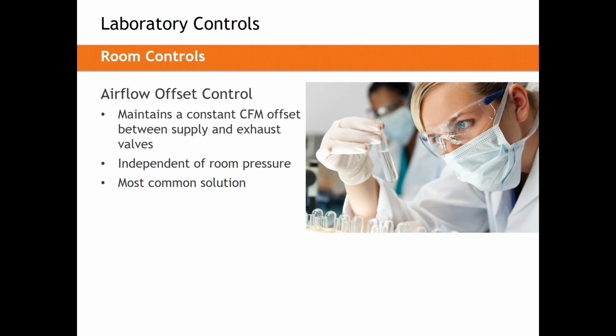Maintaining a certain pressurization is up to people. It's up to the human. Through the use of monitoring systems and regular reporting, we can ensure airflow offset control is doing its job. So in most, if not all laboratories, this is the method of control we will use. But it's also very commonly applied with an independent pressure monitor.